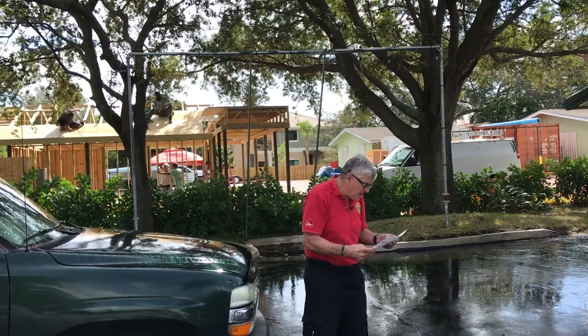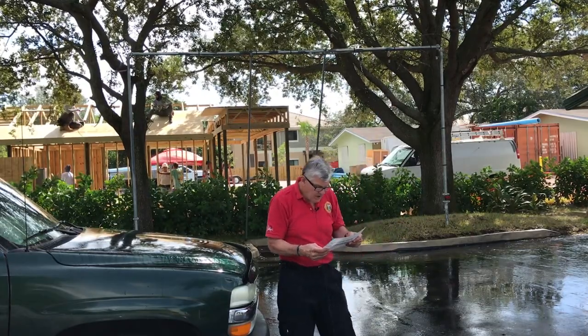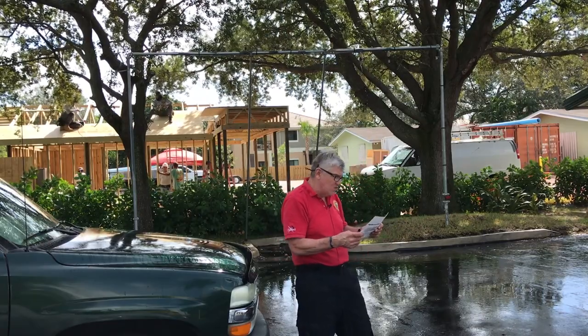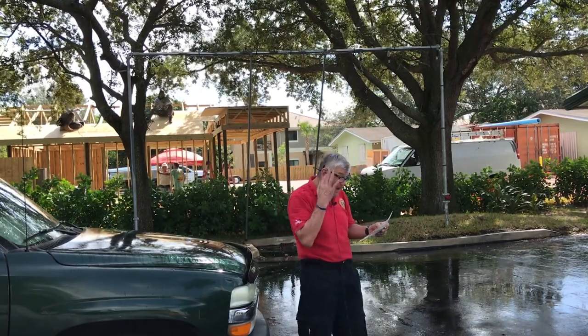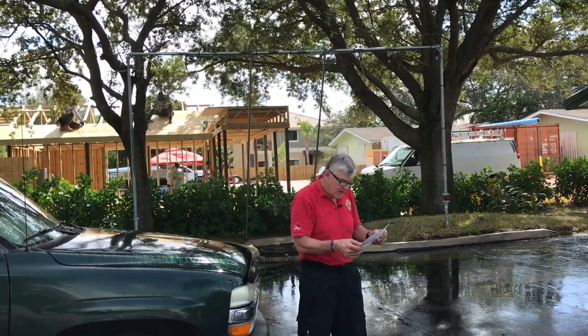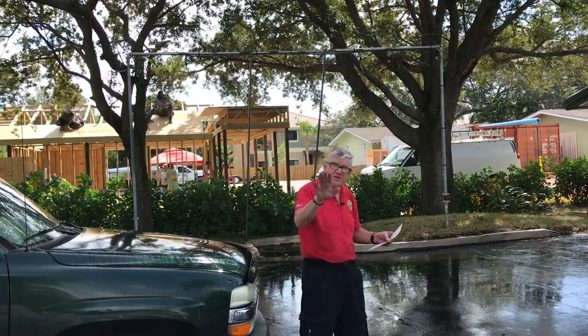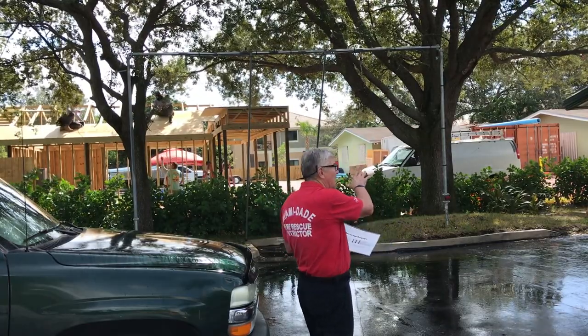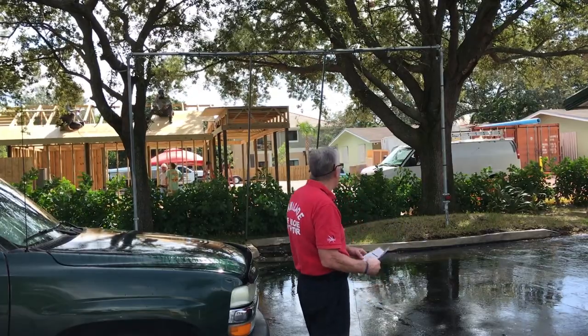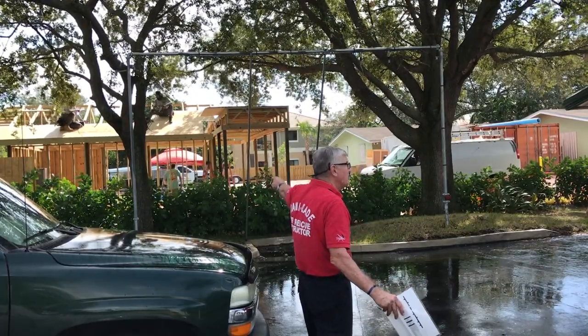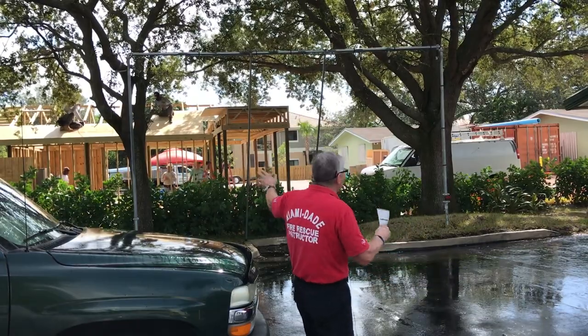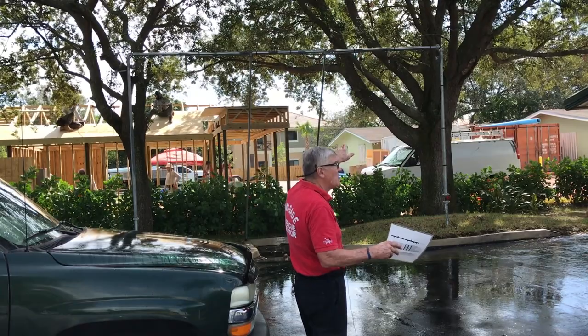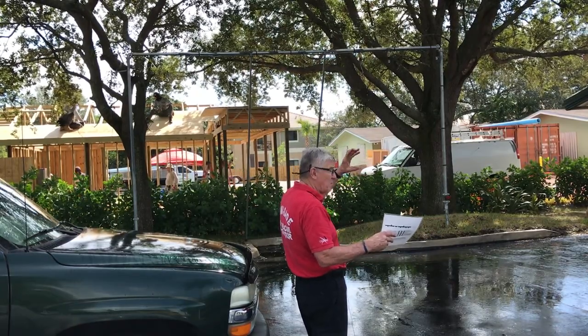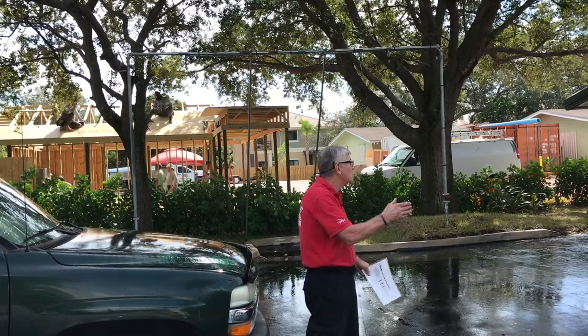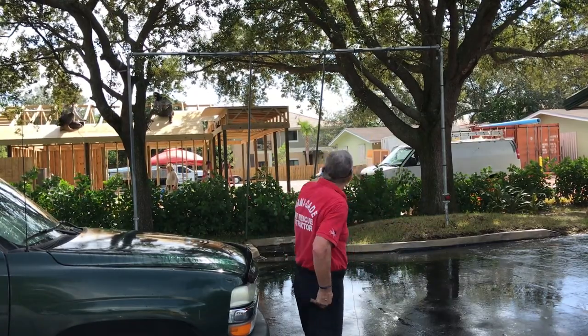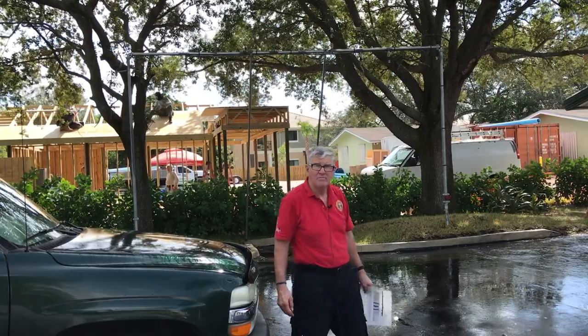All right, the last one will be another ESFR designed to flow 166 gallons a minute at 35 PSI with a 48-foot ceiling and 43-foot of storage. Now, I can tell you right now, we are not going to see this head flow 166 with this arrangement of piping. This is a demonstration of relative flows. This would have to be engineered with very robust sprinkler piping, which we do not have here. So it's relative. This would flow, obviously, more than sprinkler head number one. Go ahead.